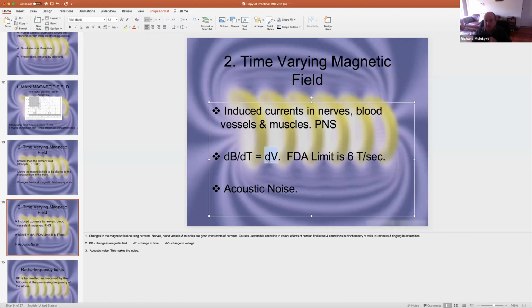Okay. Fortunately, there are limits. So the Food and Drug Administration, don't stress, say that you can't cause more than 6 Tesla per second change in magnetic field. Okay, if you do that, the machine will calculate that at the start of the sequence when we press the go button, and it will say, I'm not doing that sequence, because the change in magnetic field experienced very quickly in the body will be too fast. Okay, you experience a change in magnetic field too fast, you exceed the threshold, the machine says, I'm not scanning that because it's not safe. Okay, so that's our little catch.